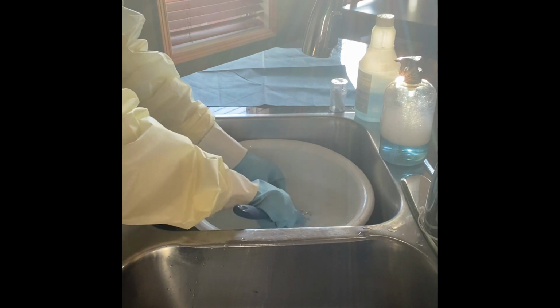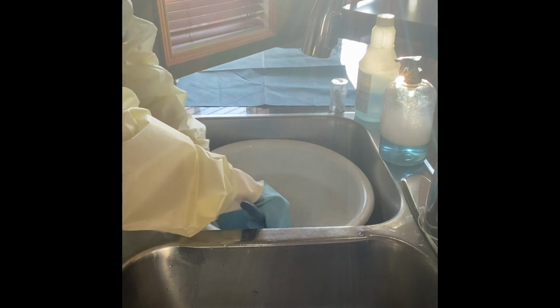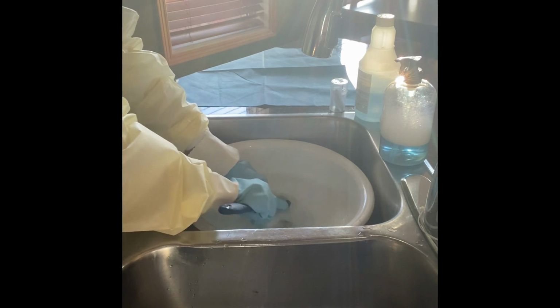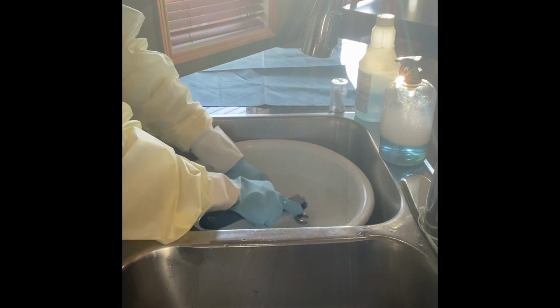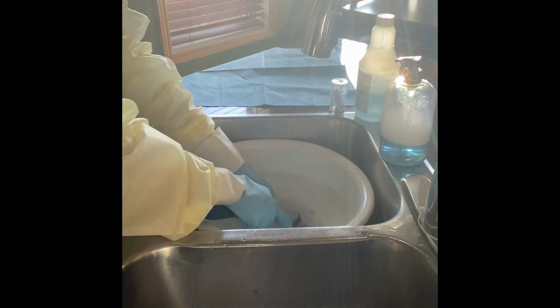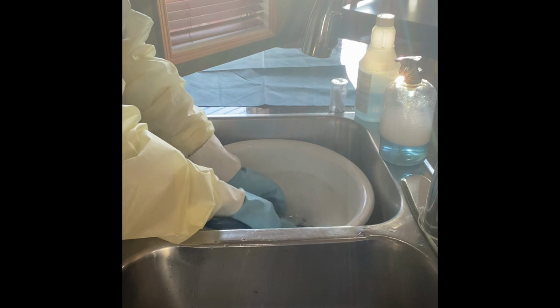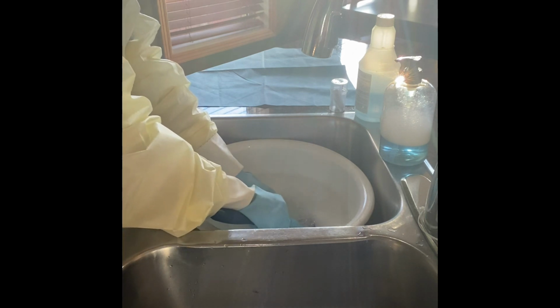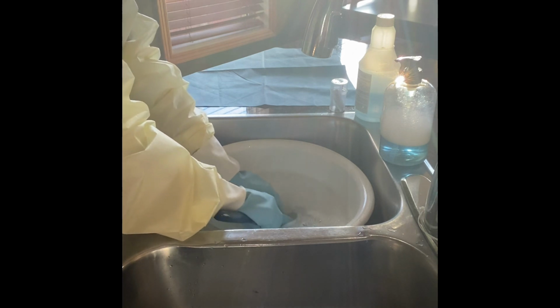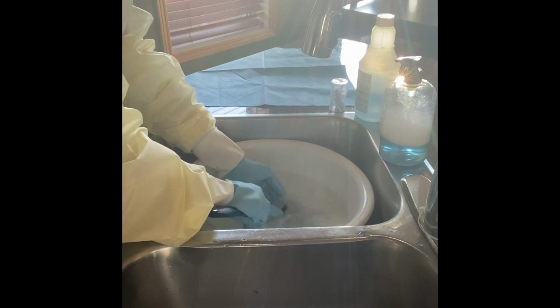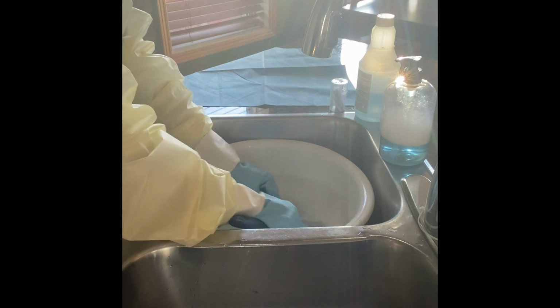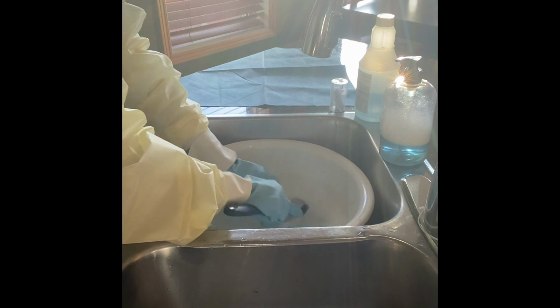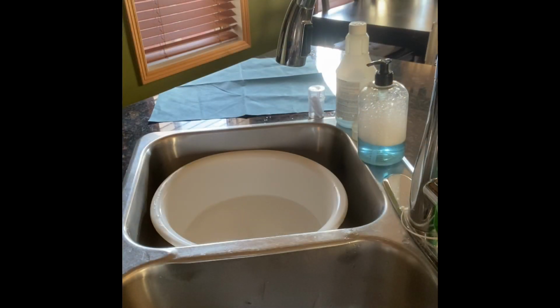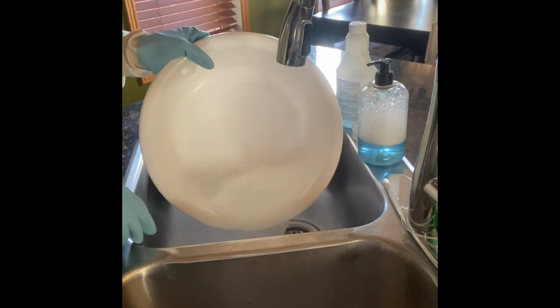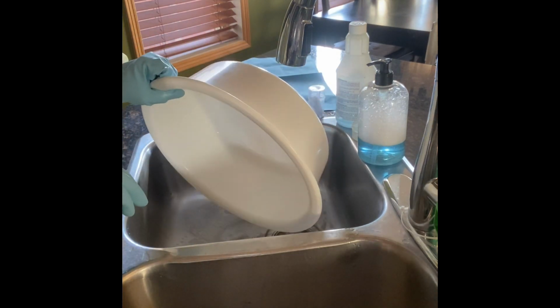Cleaning may be done manually, using detergent or enzymatic solution, water, and friction, or mechanically in an automated washer decontaminator disinfector. All manual cleaning must be done under the surface of the water to minimize splashing and aerosolization of contaminated water. Then, rinse the equipment. Make sure detergents or enzymatic cleaning solutions are discarded following each use.